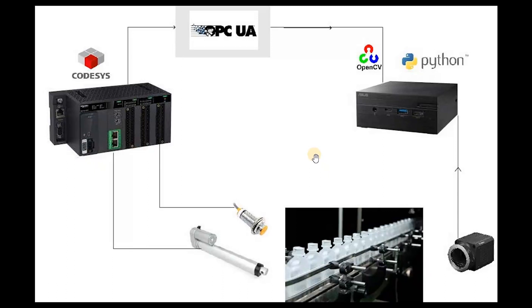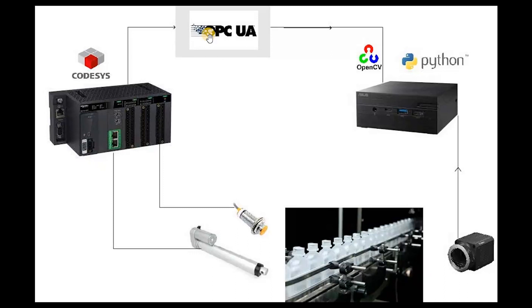Now let's say that you want to implement this project on site. What are the requirements? You're going to need a PLC of course — it doesn't matter what brand. What's important is that it can run some sort of communication protocol, because we have a mini PC that we want to communicate with, and all the algorithms for image processing will be held inside this mini PC. You can use OPC UA, Modbus TCP, or any protocol you want using Python to communicate with your PLC.